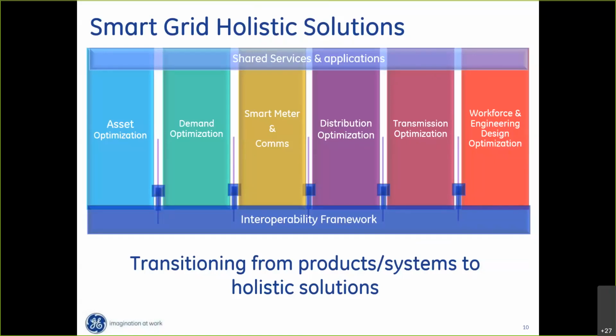Fifth, and we'll talk a lot more about this, is transmission optimization. One of the things we have been focused on with transmission is greater use of information from synchrophasors. When you can get information 40 to 50 samples per second, as opposed to SCADA data which is every 2 to 4 seconds, you have so much more insight into what's happening on the grid. We first brought that synchrophasor information into the EMS, into the SCADA system for generation transmission, to help us with the state estimator application.